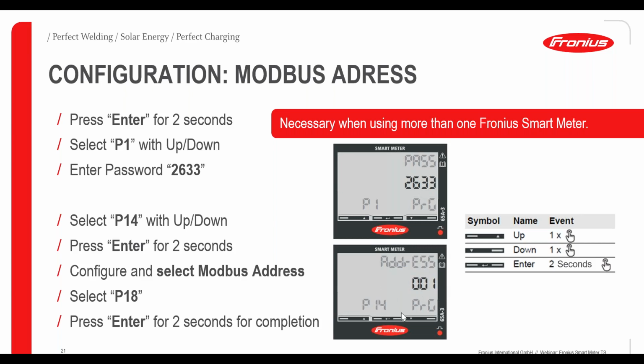And how do you do it? Via the display of the smart meter, you press Enter for 2 seconds. We have the guideline here, the Enter button in the middle. Then you choose page 1 with the up and down arrows. After that, you enter the password 2633. That's also the standard password for all of the smart meters. After that, you choose page 14 and press Enter for 2 seconds again. There you change the Modbus address from 001 to 002, for example, if it's your secondary smart meter. After that, you change to page 18 with the up and down arrows, and press Enter again for 2 seconds, and you are done with this configuration.